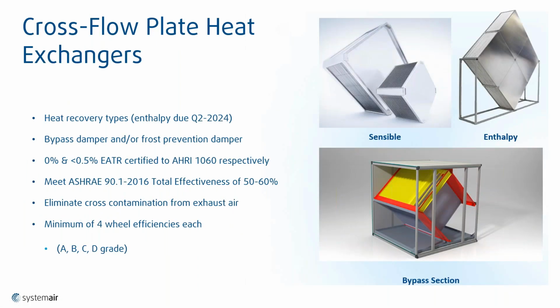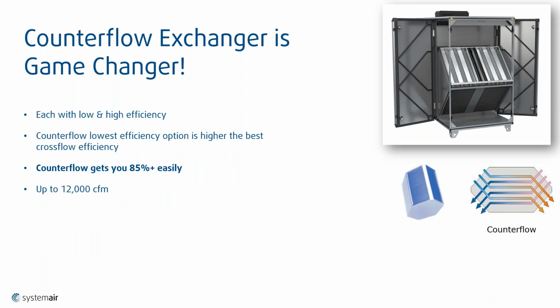Plate heat exchangers, I mean, obviously these are the standard heat exchangers which we have out there. They're sensible as well as enthalpy. Now, one of the things that I'd like to draw your attention to is obviously the counterflow heat exchangers, which are now available as well. And we can get our efficiencies as high as 85% on these counterflow exchangers. I would like to bring to your attention, though, that because of the size of the actual counterflow heat exchanger, we're going to be limited to 12,000 CFM. The unit otherwise just becomes way too big and becomes too cumbersome to actually use. So we are going to tap out at about 12,000 CFM, but you get these huge efficiencies.